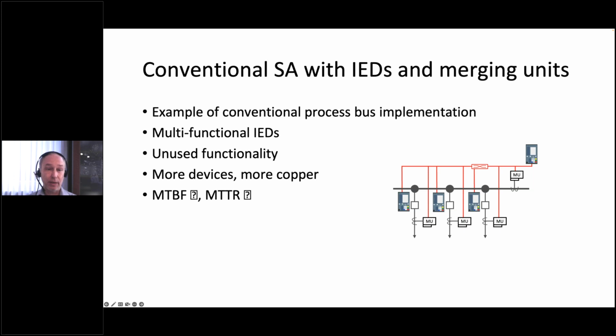In general, it can be stated that more devices means the overall mean time between failure of the substation is shorter. Also, exchanging complex IEDs in case of repair might take more time, which means the mean time to repair is higher. Next slide, please.